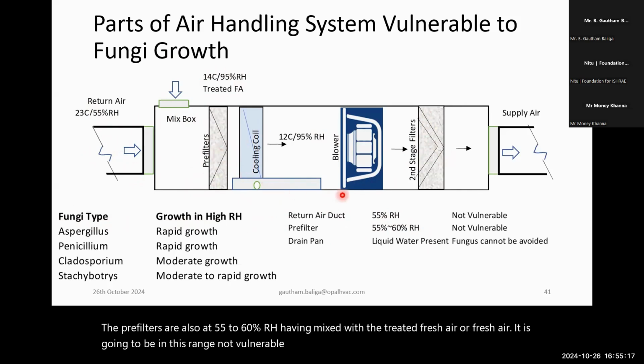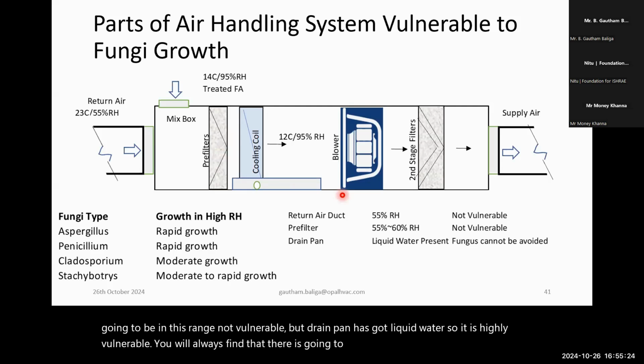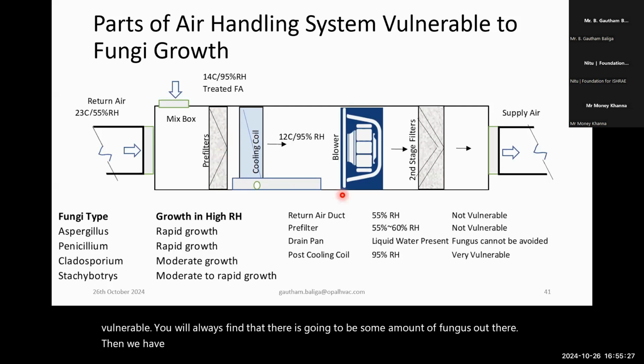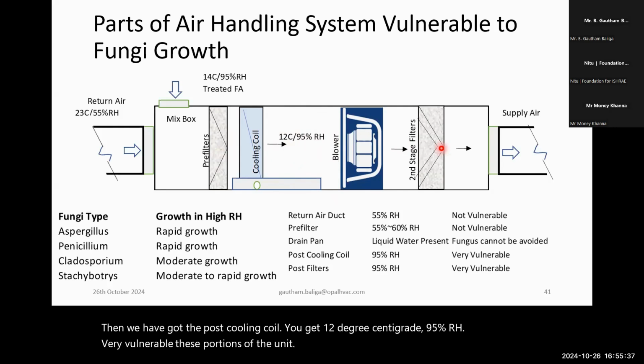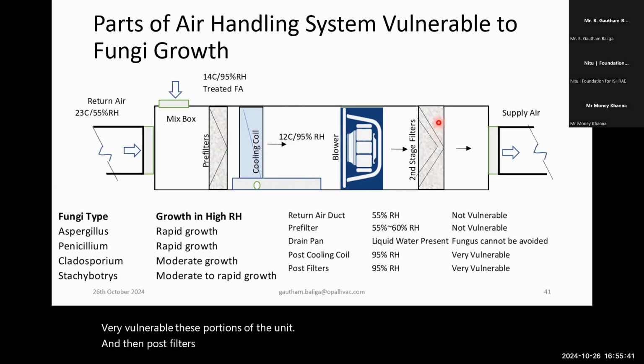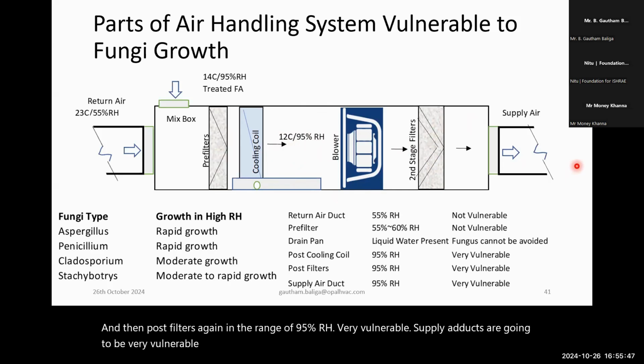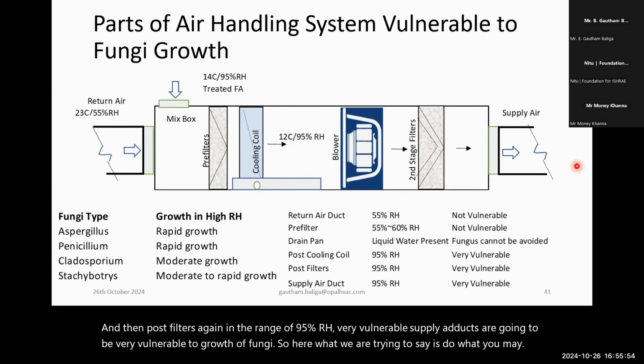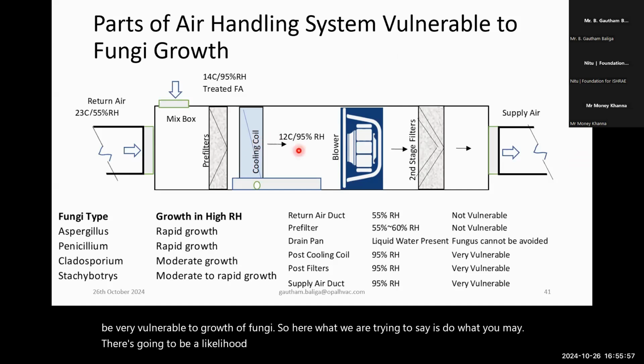But the drain pan has got liquid water, so it's highly vulnerable. You'll always find that there's going to be some amount of fungus out there. Then we have the post cooling coil. You get 12 degrees centigrade, 95% RH, very vulnerable. These portions of the air handling unit. And then post filters, again in the range of 95% RH, very vulnerable. Supply ducts are going to be very vulnerable to growth of fungi. So what we are trying to say is, do what you may, there's going to be a likelihood of fungus post the cooling coil all over the air conditioning system, right up to the supply duct.